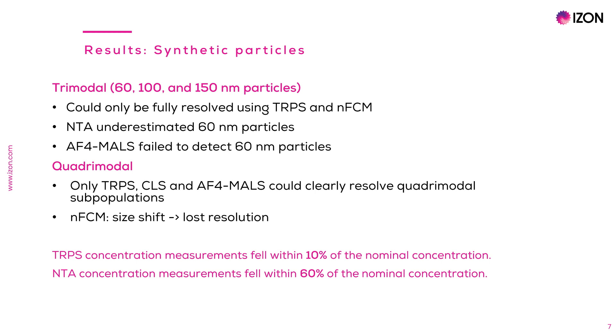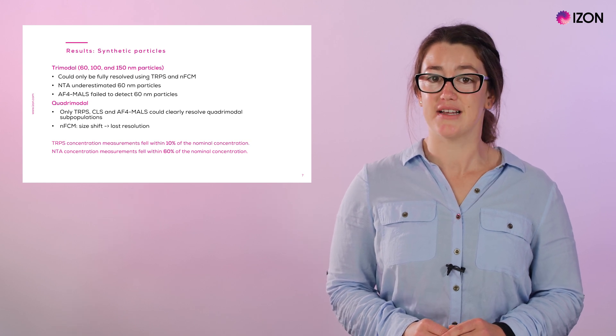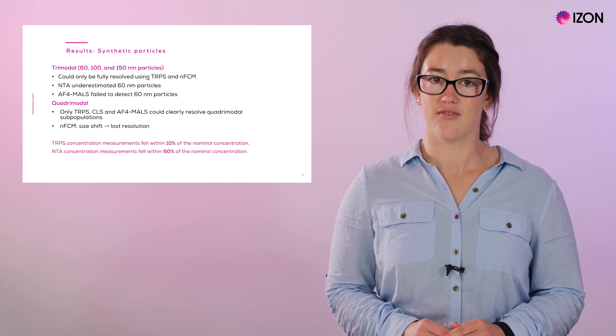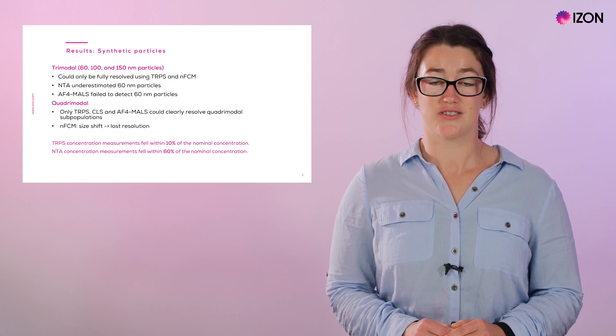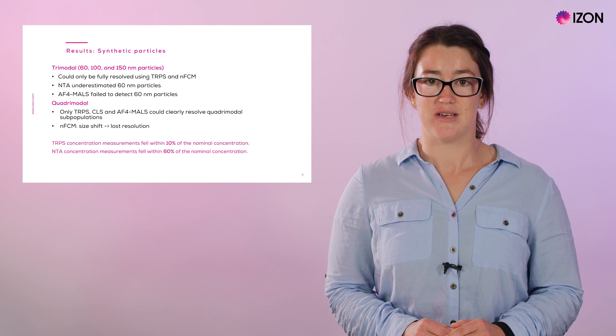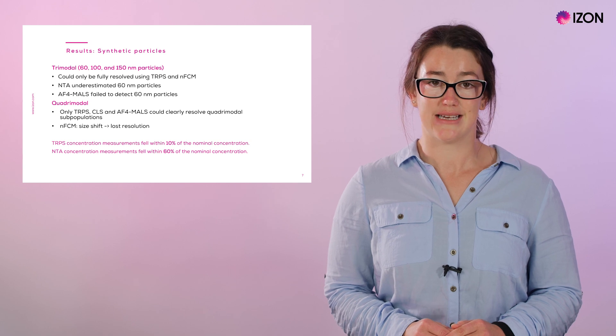When faced with a quadrimodal mixture, only TRPS, CLS, and AF4 MALS clearly resolved the subpopulations. While nanoflow cytometry was able to resolve the quadrimodal mixture, a size shift across repeated measurements caused resolution to be lost when results were averaged. Overall, this part of the study included 10 samples comprising polystyrene particles of varying sizes, ratios, and number of subpopulations. With these synthetic samples, TRPS showed good repeatability, with concentration measurements falling within 10 per cent of the nominal concentration, compared to 60 per cent for NTA.